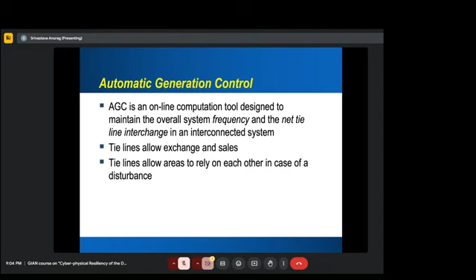So what it responds to automatically is ACE, which is area control error. It is looking at the actual frequency and planned frequency. Planned frequency is typically 50 hertz here. In the US it's 60 hertz. And then we need to estimate how much megawatt should change based on the frequency. For every system, it will be different, right? So you can look at the typical historical response and decide how much the frequency is going to change if I increase the generation by this much or decrease the generation by a certain percentage, right? So based on that, you can decide the beta and then set this in the equation.